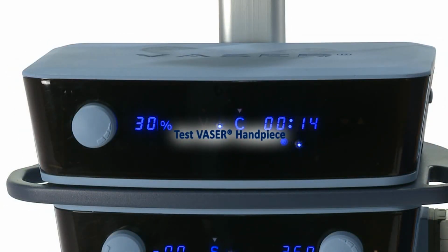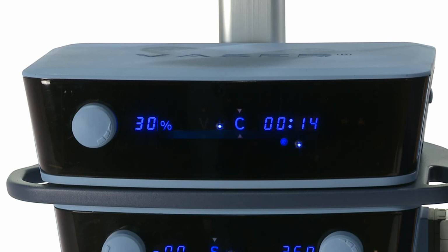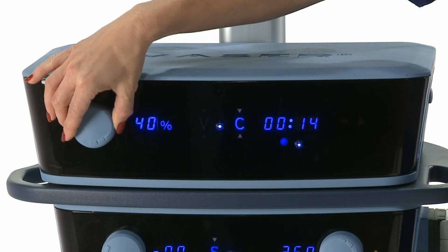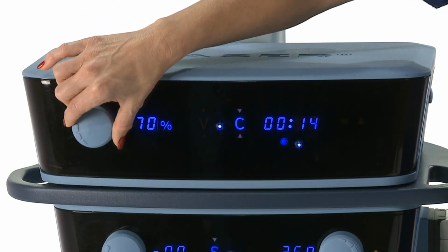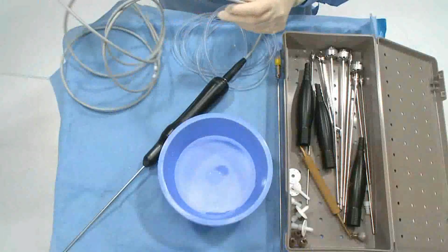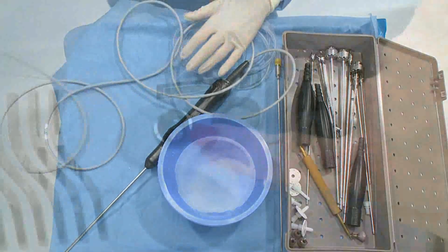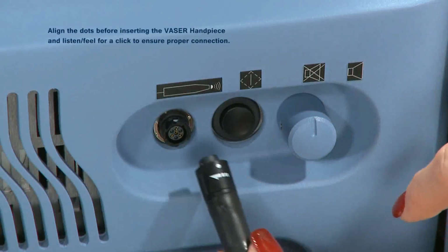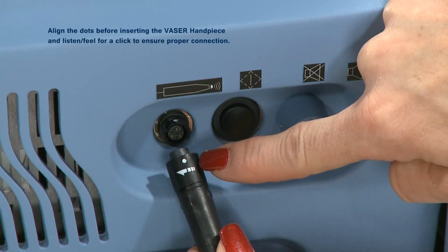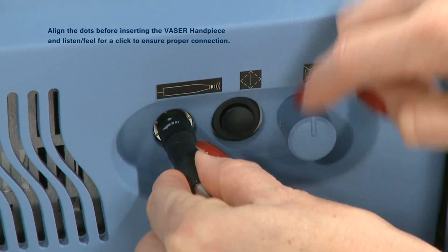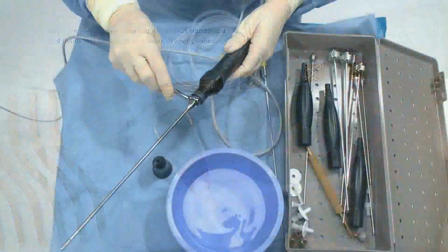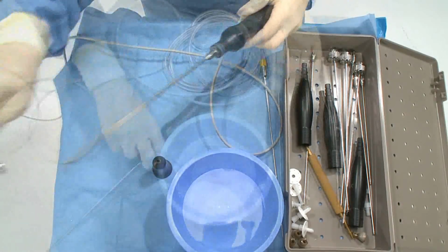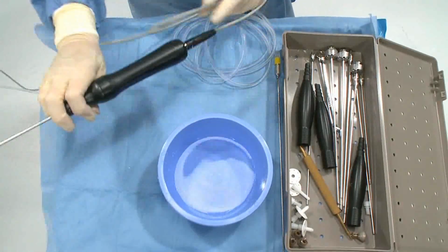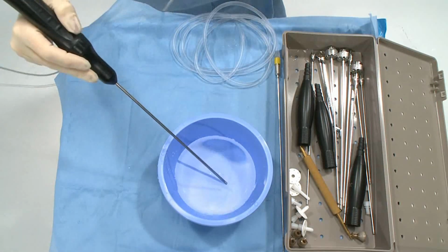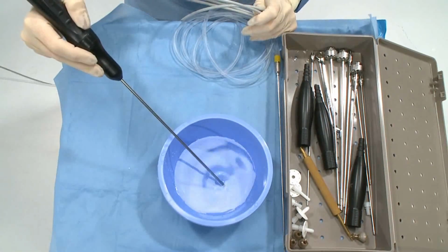Now, test the Vaser handpiece. Set the amplitude control to 70 to 80%. Pass the Vaser handpiece connector out of the sterile field. Connect it to the receptacle on the Vaser amplifier. The Vaser probe should already be attached to the Vaser handpiece. In the sterile field, completely immerse the tip of the probe into a cup of sterile water.